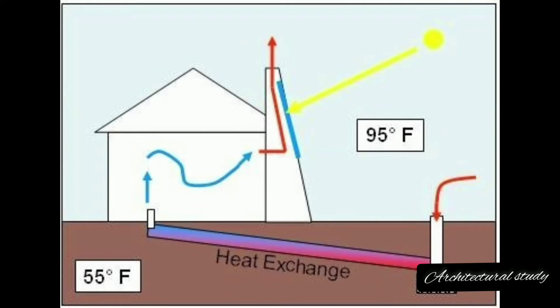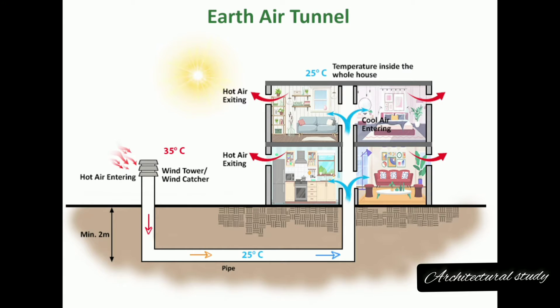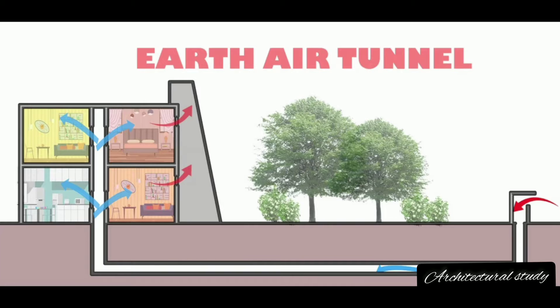The recommended depth for EATS is generally 3 to 6 meters, though the ideal placement depends on climate, soil type, and water table. The Earth's temperature gradually decreases with depth, but within this range, variations have minimal impact on performance. Consulting an engineer is key for optimal design and depth selection.